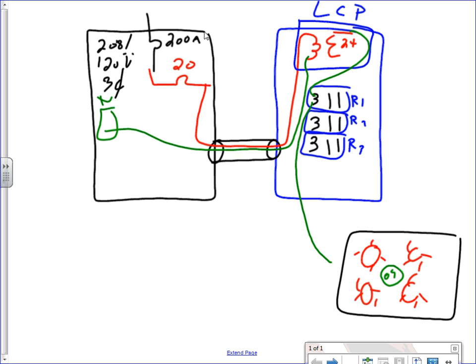From the other side of the coil you go to the occupancy sensor, and from the other side of the occupancy sensor back to the second side of the coil — so the occupancy sensor acts like a switch. When it senses you're moving, it brings 24 volts across the coil. When that 24 volts is across the coil, the coil closes. But we still haven't connected the light — the coil closing is just the control side.